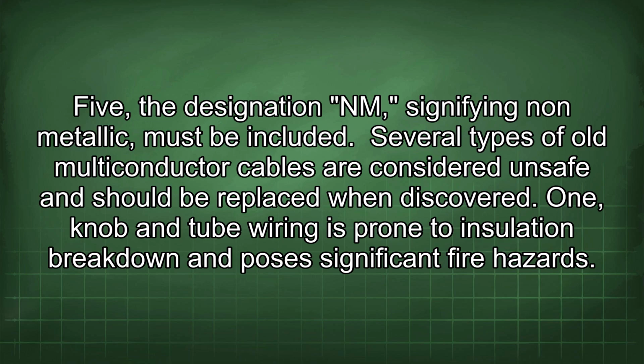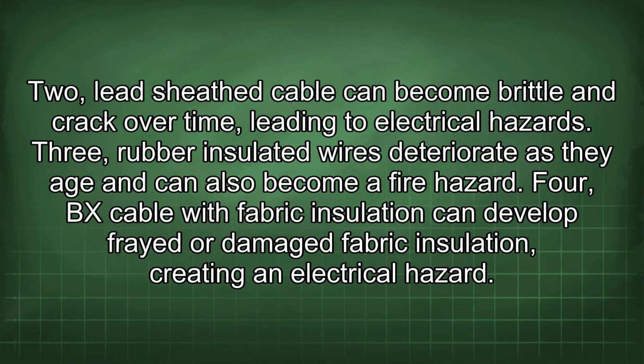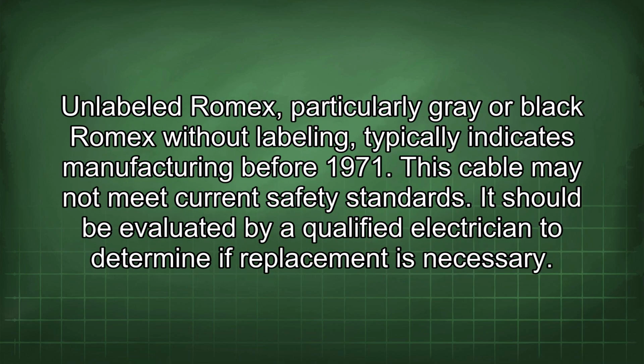Several types of old multi-conductor cables are considered unsafe and should be replaced when discovered. 1. Knob and tube wiring is prone to insulation breakdown and poses significant fire hazards. 2. Lead sheath cable can become brittle and crack over time, leading to electrical hazards. 3. Rubber insulated wires deteriorate as they age and can also become a fire hazard. 4. BX cable with fabric insulation can develop frayed or damaged fabric insulation, creating an electrical hazard. Unlabeled Romex, particularly grey or black Romex without labeling, typically indicates manufacturing before 1971. This cable may not meet current safety standards. It should be evaluated by a qualified electrician to determine if replacement is necessary.